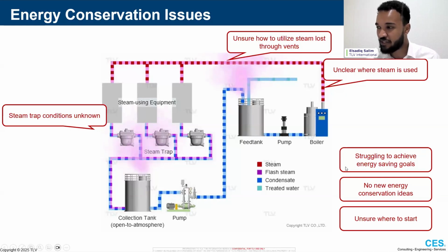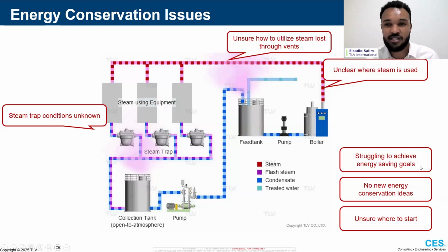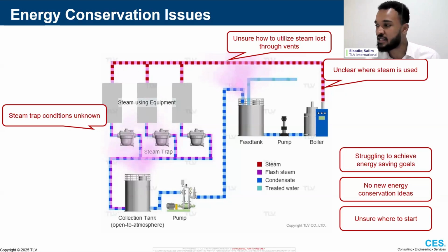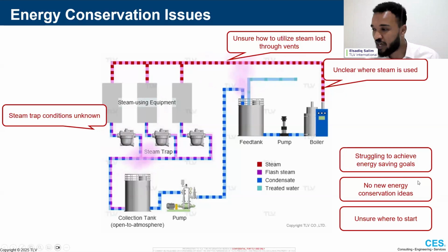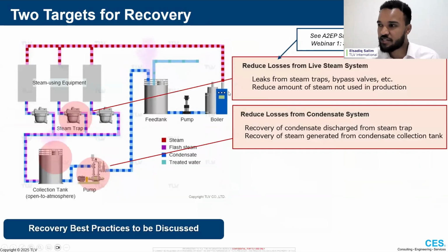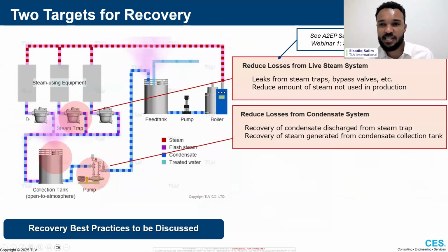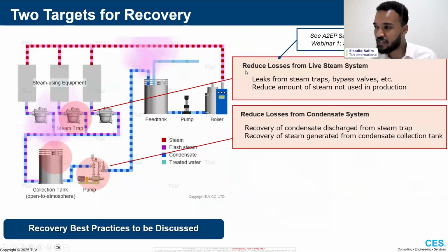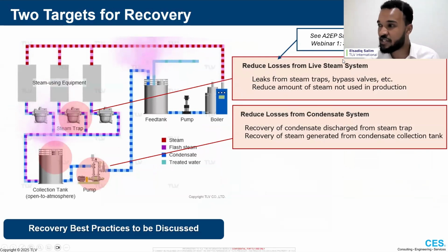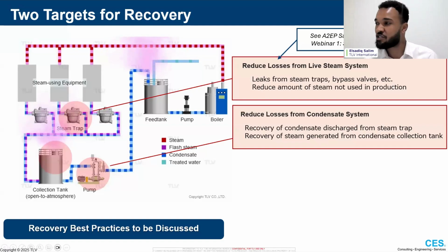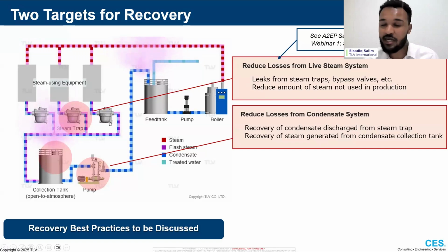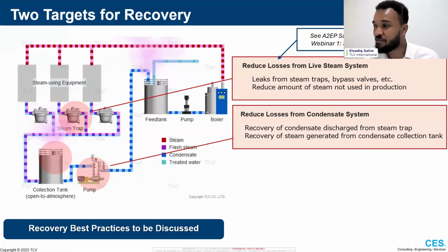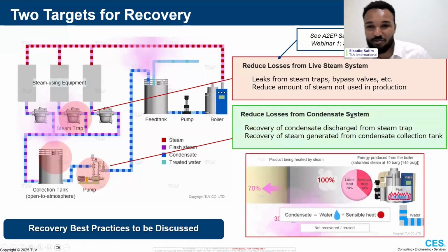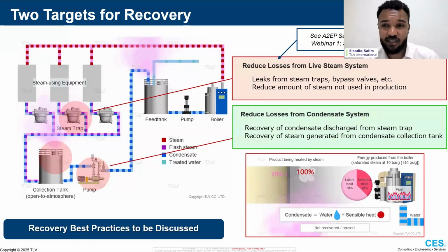And then from a top level perspective as well, we get some energy saving goals. Many sites, especially nowadays, it's great to see they've got carbon emissions targets, net zero targets, and energy emissions goals, but it's sometimes difficult to find areas where we can start on this journey. So our advice in any kind of steam system analysis is to split it into two to help fragment the issue. Firstly, looking at reducing losses from the live steam system. And that's something we covered in a bit of detail in the previous webinar from A2EP. You can catch the recording online. That's where we're talking about steam traps, steam trap management, and how we can make sure that we're not losing steam from our live steam system. Our focus today is going to be on the condensate system and how we can make sure that we're capturing absolutely as much waste heat as we can from that condensate system. Primarily, first point of call, and we saw it on Alan's side as well, the potential of just recovering condensate in the first place.